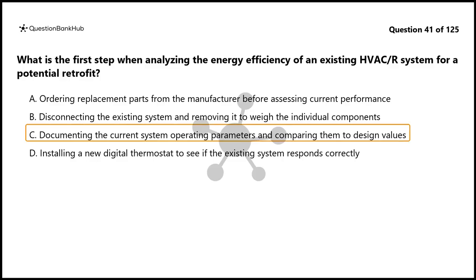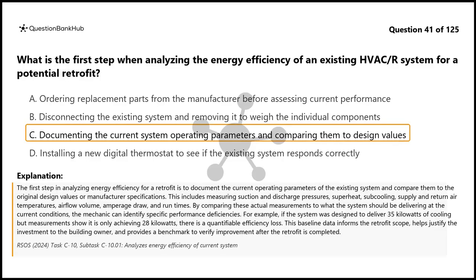The correct answer is C. The first step in analyzing energy efficiency for a retrofit is to document the current operating parameters of the existing system and compare them to the original design values or manufacturer specifications. This includes measuring suction and discharge pressures, superheat, subcooling, supply and return air temperatures, airflow volume, amperage draw, and run times.